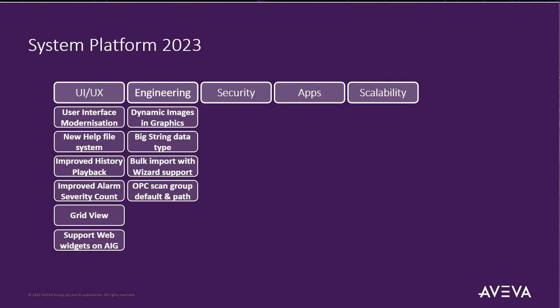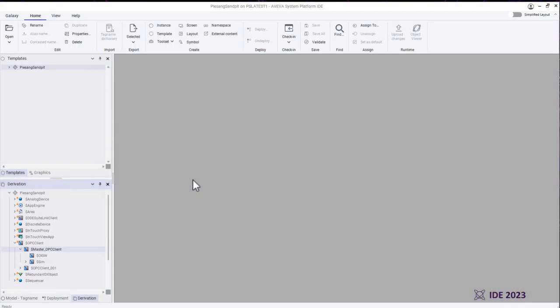The problem was these things had different behaviors. They had default scan groups, and the way that you would build them is you would build a hierarchy of these DI objects, and your whole reference path had to have that hierarchy, backplane.cpu.io, and those kind of things, which means that if you wanted to swap it out with an OI server, you would have to redo all your IO references, either in the CSV if it's direct, or in the alias list if it's through alias list, or you would have to adjust your scripts, which made it painful to adopt OPC client working on top of OI server.